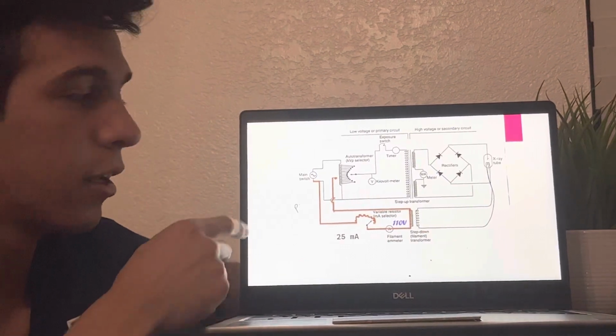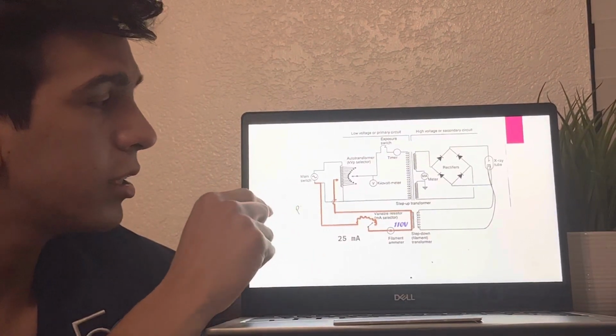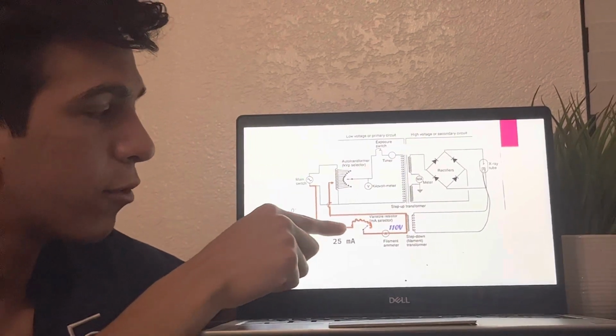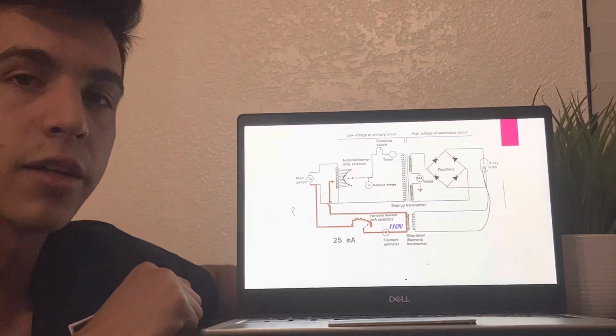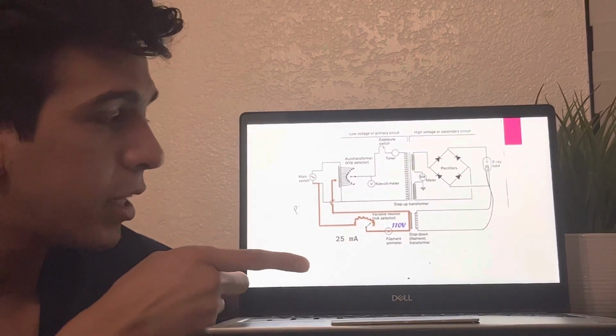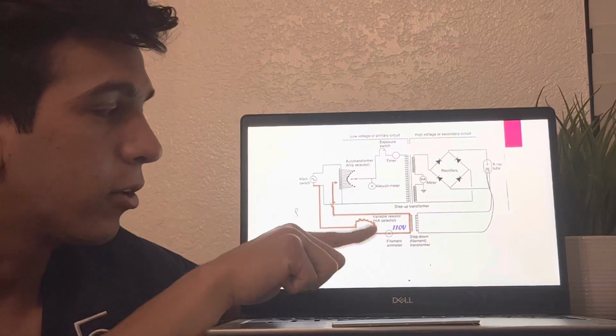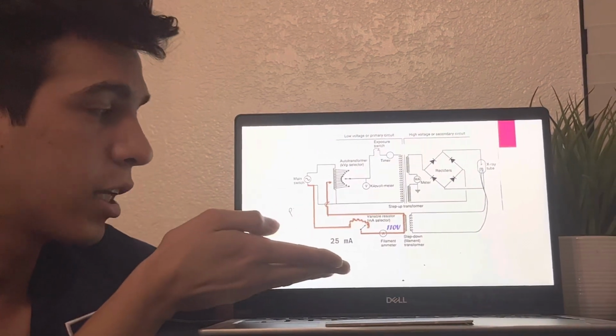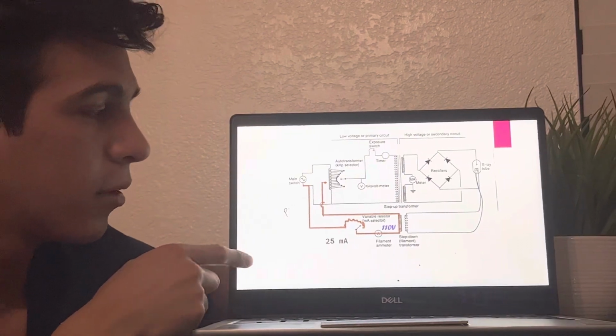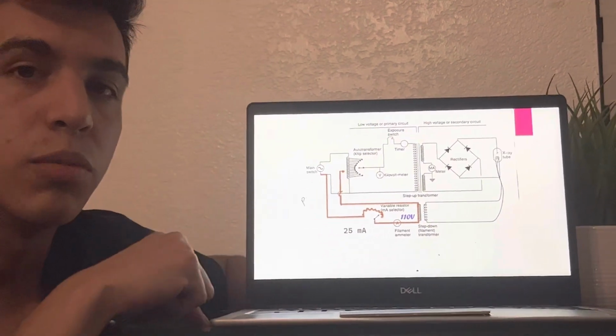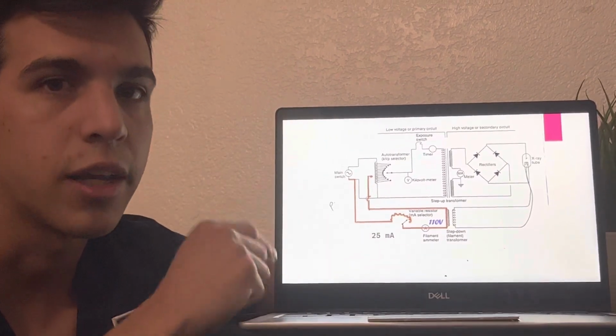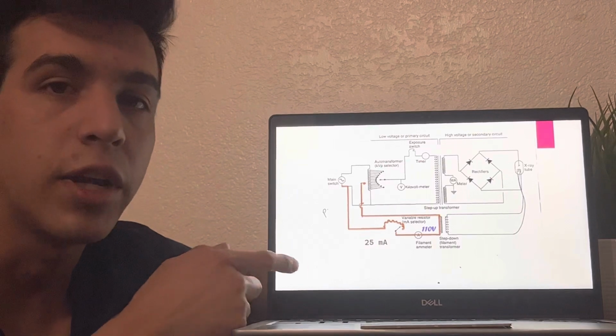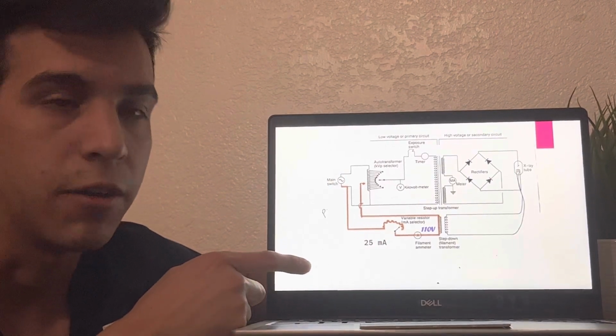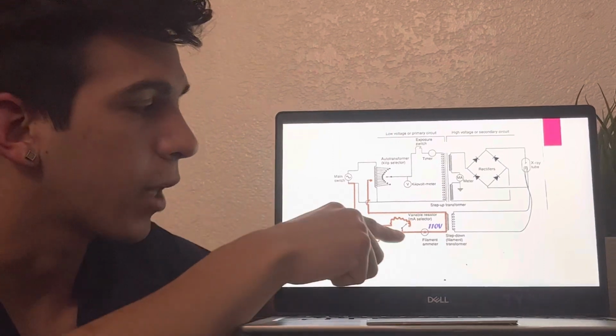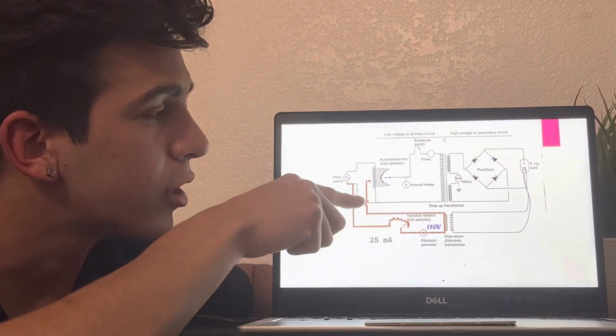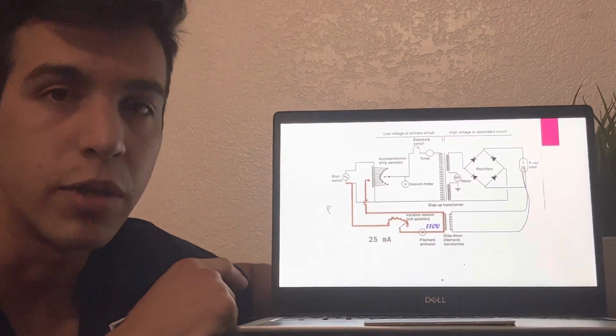First, we're going to be discussing the filament current. It runs from the main switch down over to the variable resistor or MA selector. The MA selector is basically this little dial, and it's going to be selecting, for our example, 25 milliamperage. And it goes to the notches based on the settings that you put in. So let's say we put in more, it would go to the correct setting that we put in. The filament ammeter is going to read that as the correct setting if it goes to the correct setting. After that, it's going to go up through these coils, over this way, into the auto transformer or kVp selector.